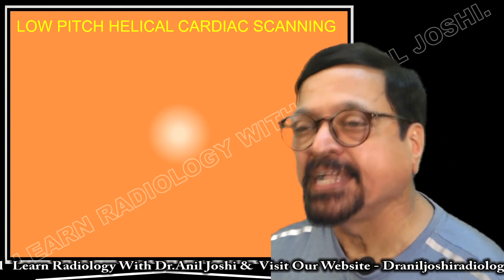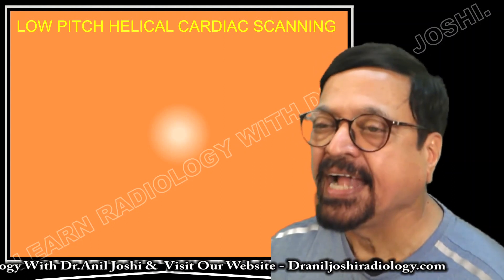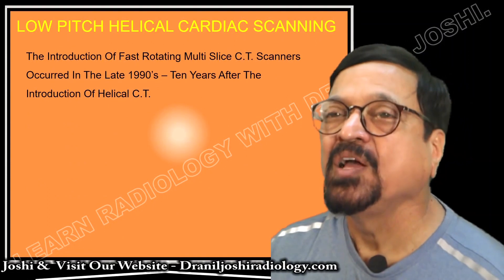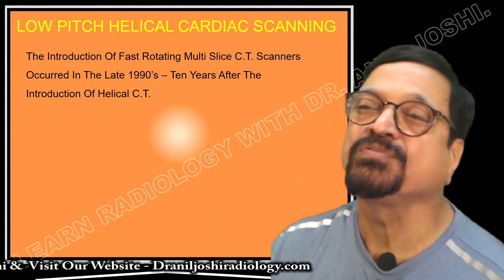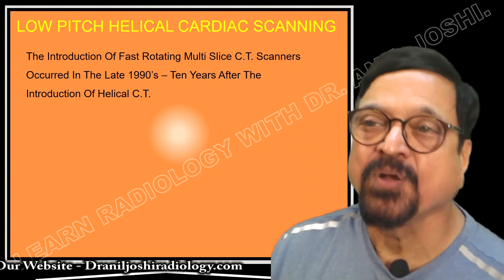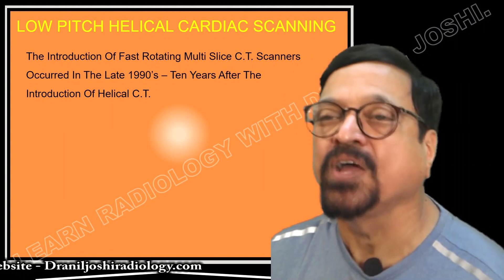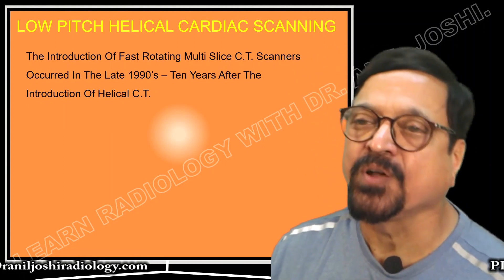There are certain specifications required for cardiac CT. It has all the requirements of a fast-moving CT scan, but it has one additional requirement: to deliver images in a fraction of a second when required, and this is triggered by the ECG. This special application of cardiac CT represents the highest point of slip ring technology. The introduction of fast rotating multi-slice CT scanners occurred in the late 1990s, ten years after the introduction of helical CT.